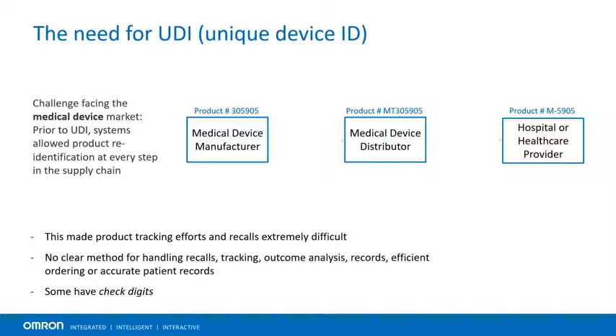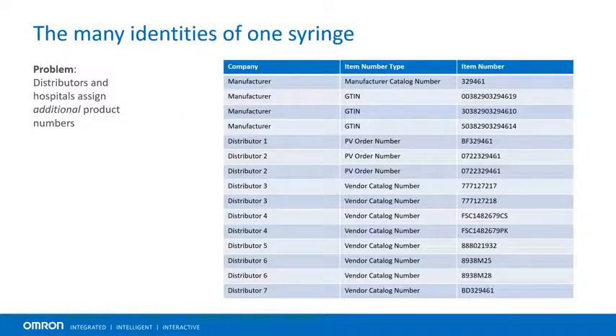To answer the question of why the FDA found it necessary to introduce the Unique Device ID mandate: one needs to look at the challenge facing the medical device market prior to UDI. At that time, systems allowed medical devices to be re-identified virtually at every step in the supply chain, which made product tracking or recall efforts extremely difficult. To make the challenge even more clear, one only needs to look at the many part numbers under which a single product from a single manufacturer may have been present in the market, depending on whether one referenced the original manufacturing part number or the various part numbers under which the same product may have been marketed by various vendors.